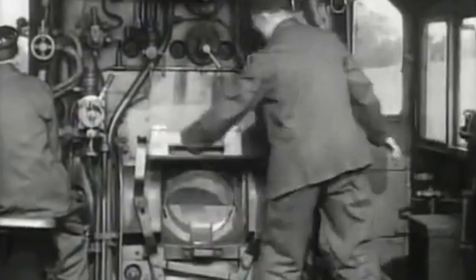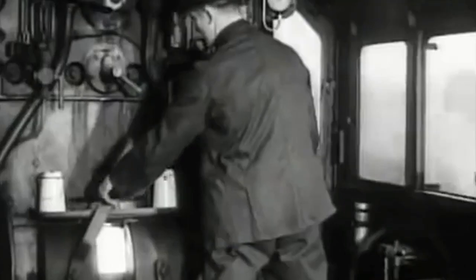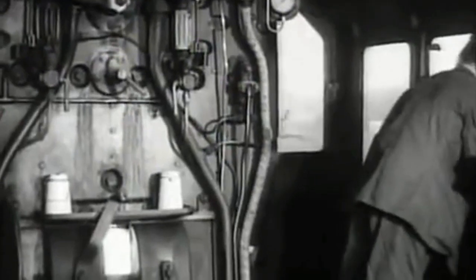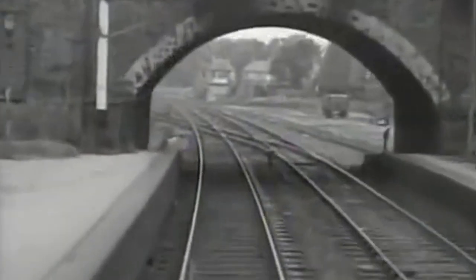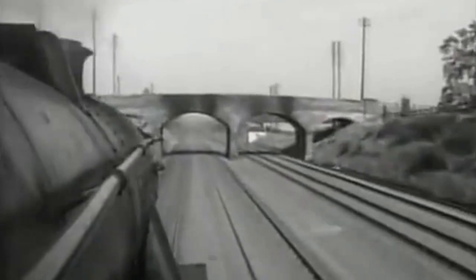What about how often? Adjust the fire hole doors until the smoke is light grey. By the time the smoke disappears — which is in about two minutes — it is time to fire again. That is how often. The smoke has gone, so two minutes have passed: it is time to fire again.